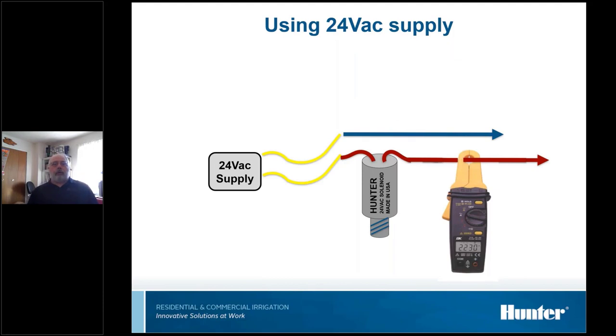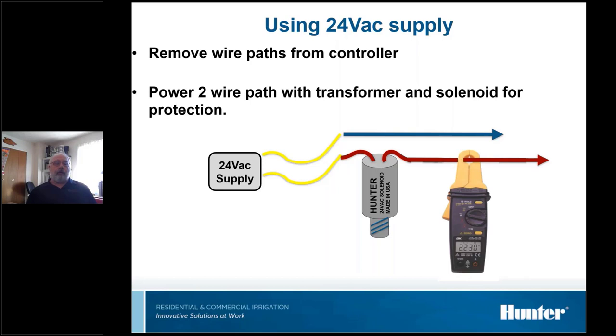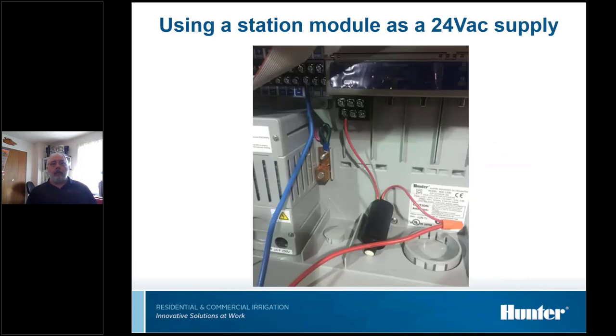Just showing what it looks like if you put the solenoid in line. Like I say, it doesn't matter if you hook it to the red or blue wire. It really makes no difference. And then get a reading, and the clamp-on is only on one of the wires. Again, it doesn't matter which one. Make sure you take them off of the controller first. Put the solenoid in for protection, especially if you're using a smaller transformer. Then you can check anywhere.